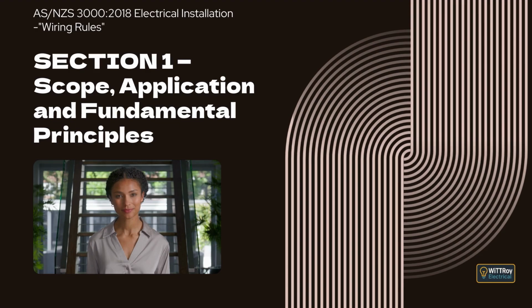Clause 1.5.4.6 Protection by placing out of reach. This method relies on ensuring the live parts are positioned far enough away that a person cannot physically reach them from a normal working or standing position. It can only be used where access is restricted to competent persons or people under supervision. Simultaneously accessible live parts of different voltages must not be within arm's reach. Arm's reach means a radius of 2.5 meters from where a person is standing or can move within the space, including vertical reach. If obstacles or working conditions change the normal reach area, then distances must be increased to keep live parts safely out of reach. Clause 1.5.5 Fault protection.